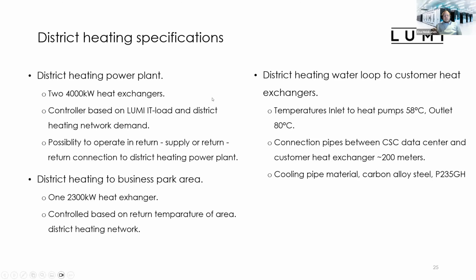So inlet for the heat pumps, we are trying to keep it stable at 58 degrees Celsius, and outlet is close to 80 degrees all the time. And connection pipes between our data center customer heat exchangers are approximately 200 meters, so it was very cost effective to implement this heat reuse in this business park area. And these cooling pipes are done in carbon alloy steel, so those are not stainless ones.